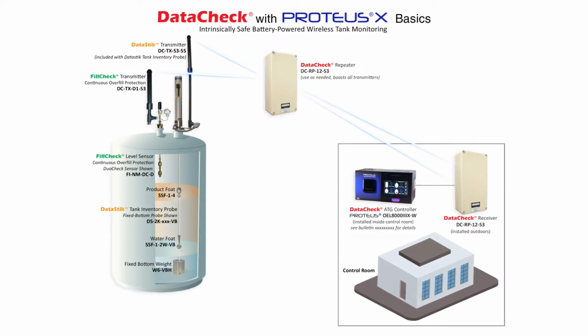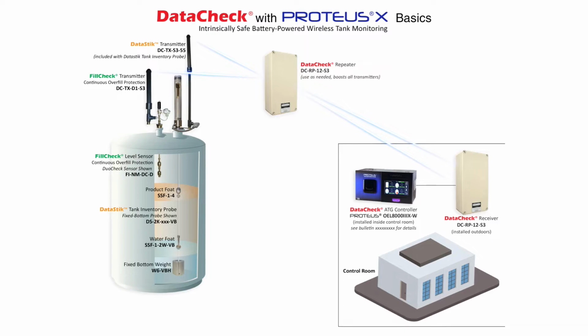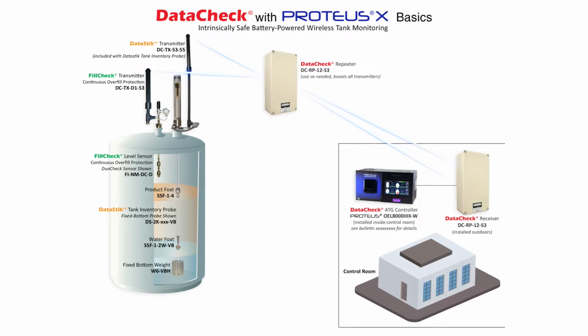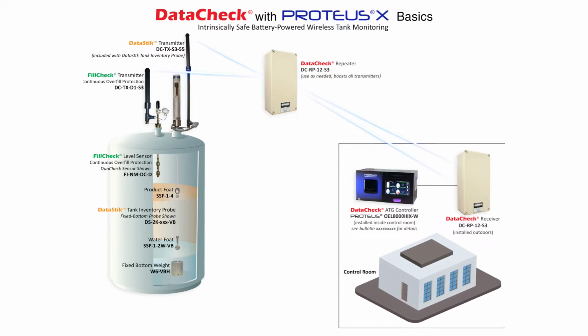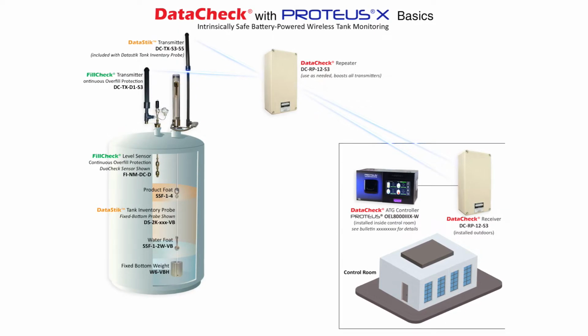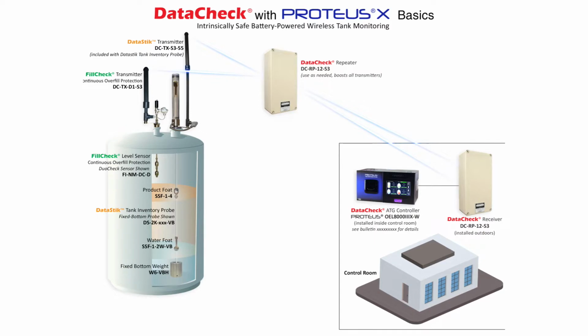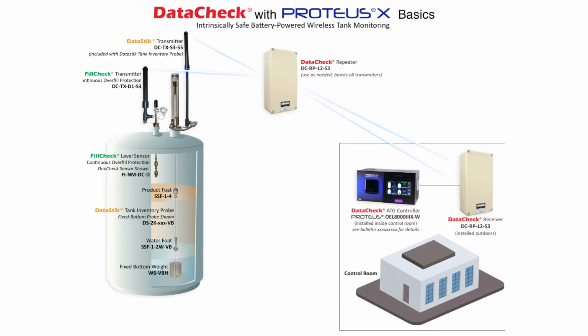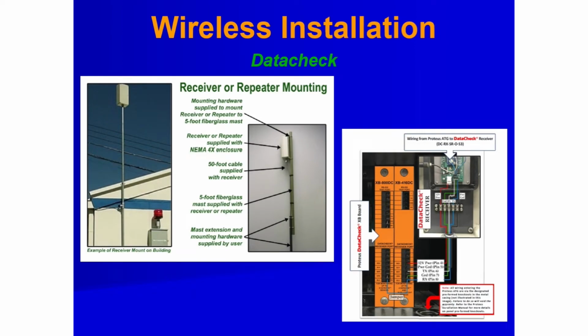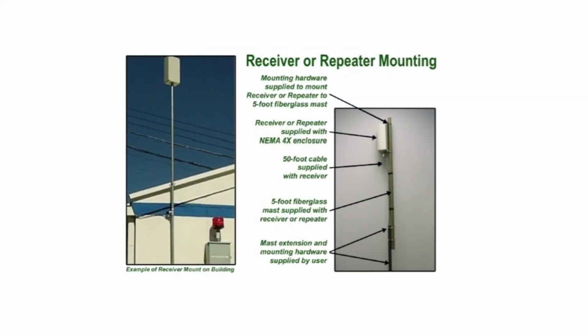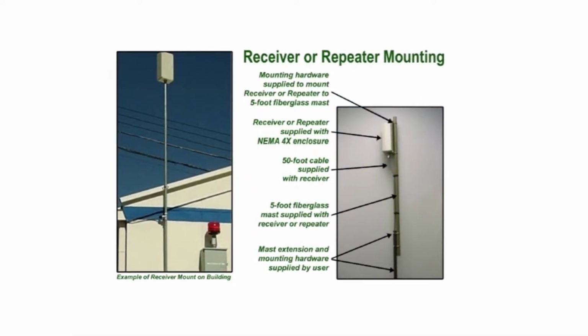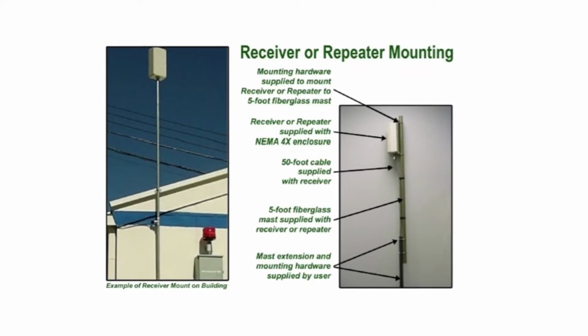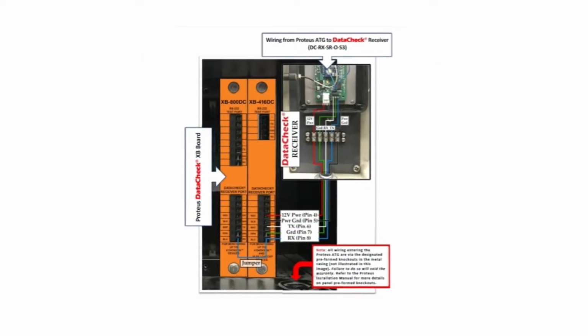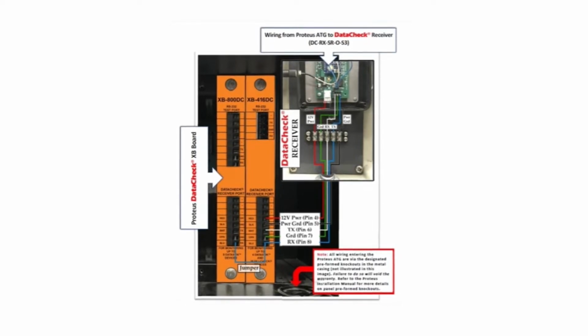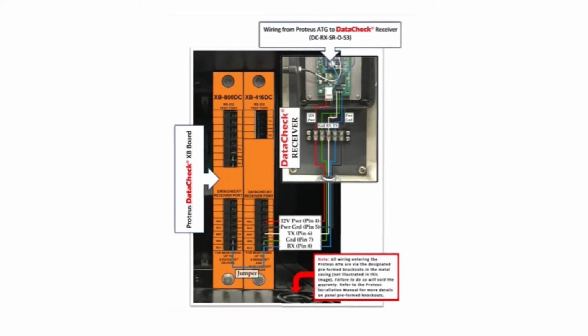Wireless probes operate in a similar fashion to wired probes, but use a wireless transmitter, or DataStik, to communicate with the controller. Level float sensors can be installed for overfill protection and also utilize a wireless transmitter, or FillCheck, to communicate with the controller. Wireless receivers are generally mounted outside of the building where the controller is located. If additional range is needed, or there is a limited line of sight, a repeater can be located between the transmitters and receiver. The receiver gets wired to either an XB416 DC or XB800 DC interface board.